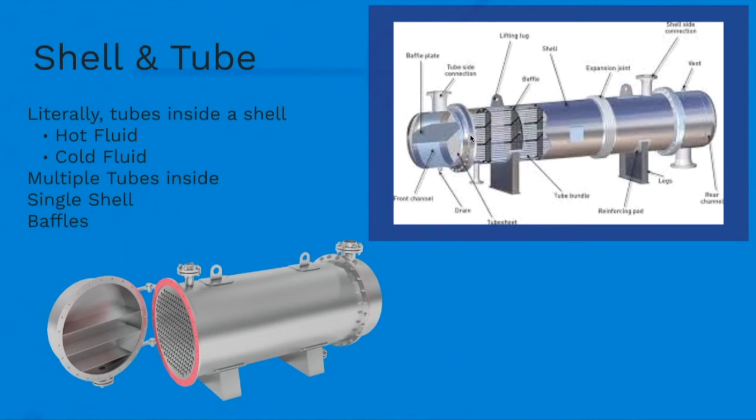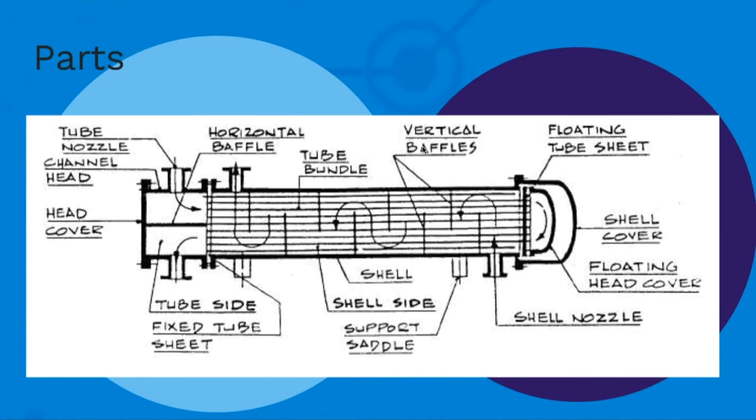Let me continue with the parts of a heat exchanger. You have the tube or nozzle where the inlet fluid enters. There's a head cover that prevents the fluid from going directly through, forcing it through the baffles. These baffles allow fluid movement—the more time it takes, the more time for heat transfer. Eventually the fluid flows all the way back.